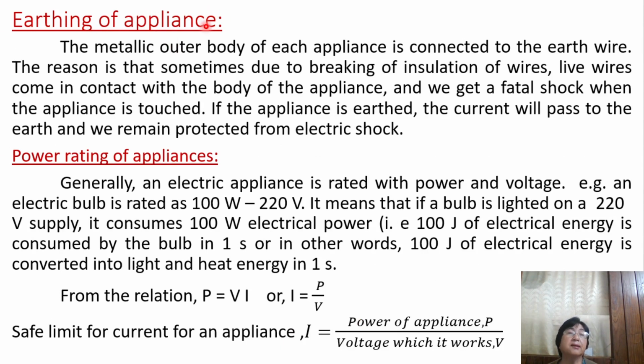Earthing of an appliance: remember, all appliances have a metallic case. Usually the metallic case has paint, so we need to remove the paint, and there is usually a connection in this metallic case for the earth wire. So the earth wire does not go together with the live and neutral wire in the appliance, but is usually connected to the metallic case of the appliance.